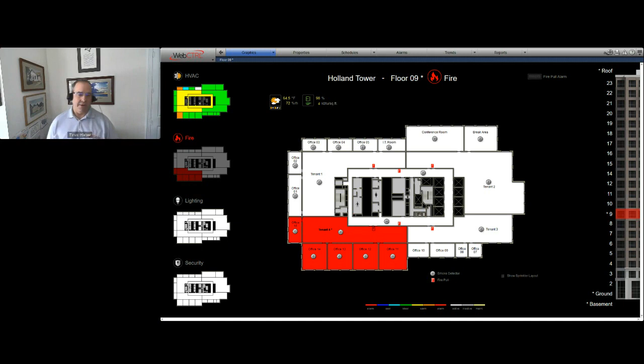So just to drive a little further on what Mike's talking about, with our field server bridge, it's a bridging unit that takes the information digitally and pushes it out through this field server unit. One option is BACnet, there's also Modbus and TCP/IP communication. So it doesn't have to just go to the building automation system. It could even go into, say, a security access control system that has graphics at the property, giving that digital connection to another solution at your property so those other platforms can also utilize emailing functions.